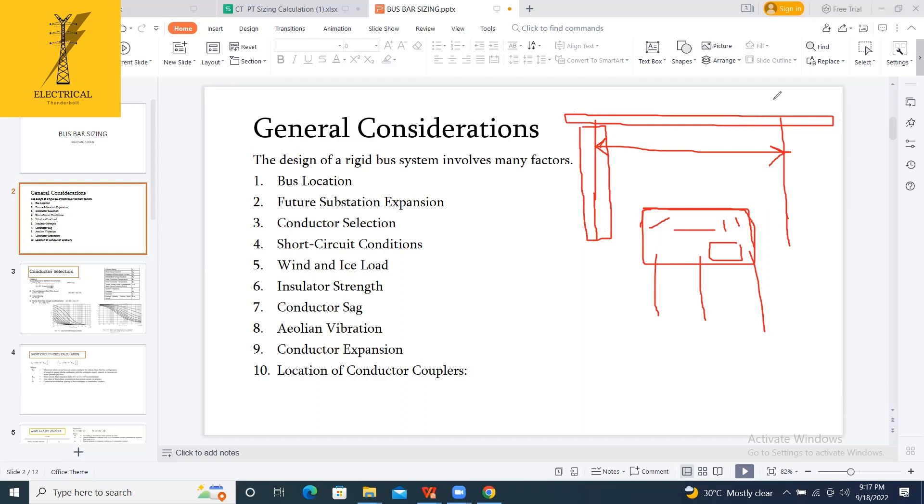How can I know this? If you know the load acting on this, then only you will come to know this. What are the loads? Obviously one is a short circuit force, and other one is if your project is prone to ice loading or wind loading. So that's also one more factor, load conditions you have to consider.